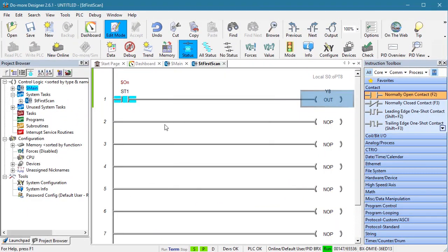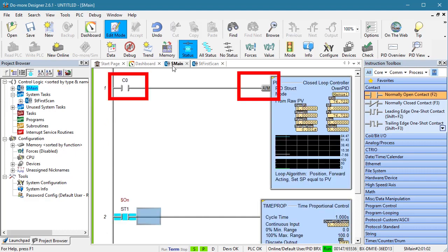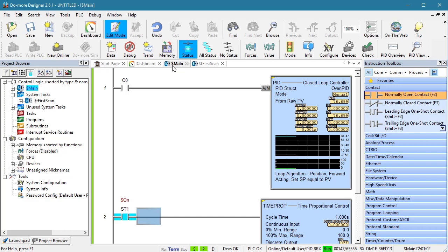Now, nothing is happening because PID is in manual mode, which means we are controlling the PID output, not the PID instruction. And that's a key point. Once the instruction is in place, PID is always running. The auto-manual selection just decides if PID is automatically controlling the output of the instruction or if we are manually controlling the output of the instruction.